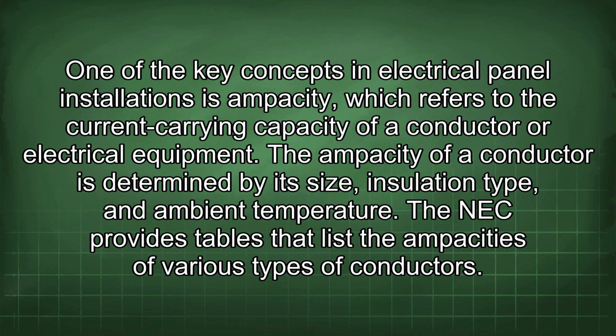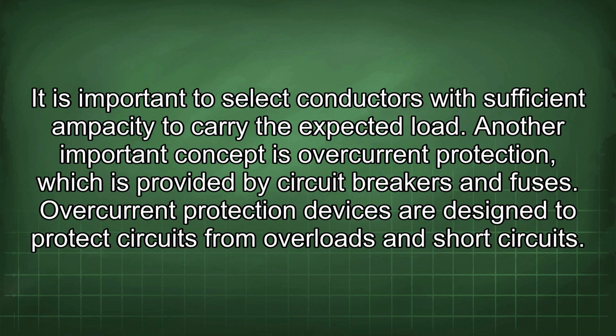One of the key concepts in electrical panel installations is ampacity, which refers to the current carrying capacity of a conductor or electrical equipment. The ampacity of a conductor is determined by its size, insulation type, and ambient temperature. The NEC provides tables that list the ampacities of various types of conductors. It is important to select conductors with sufficient ampacity to carry the expected load.